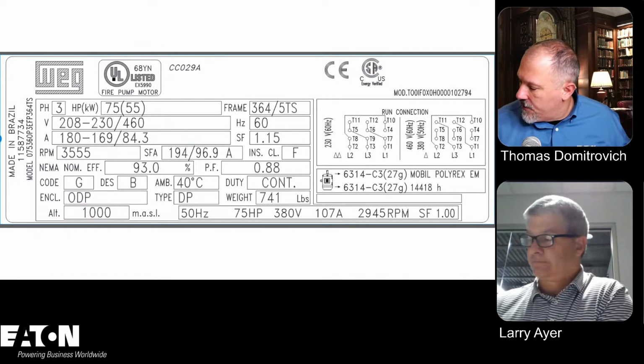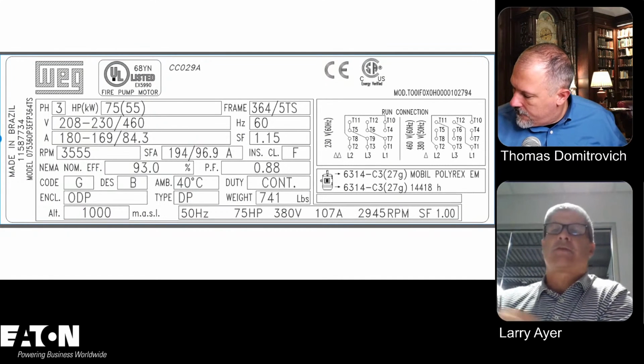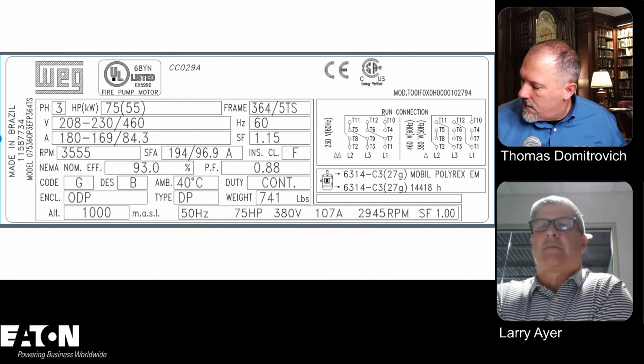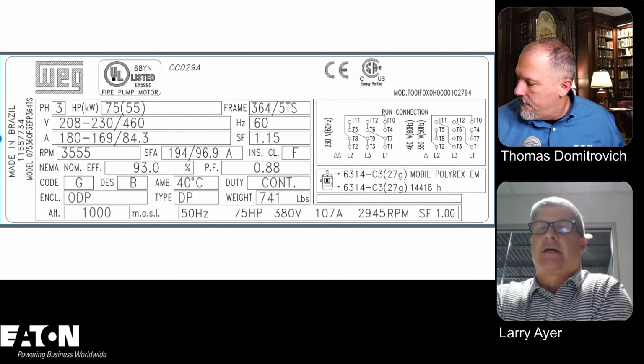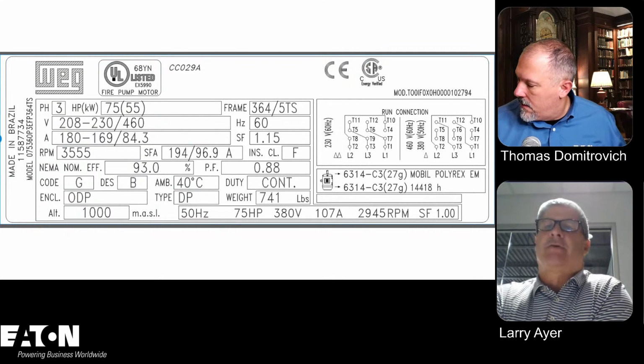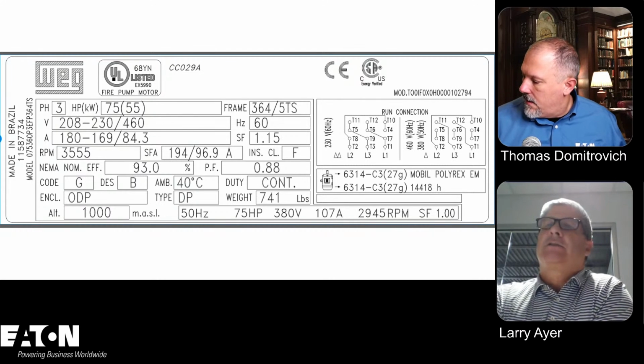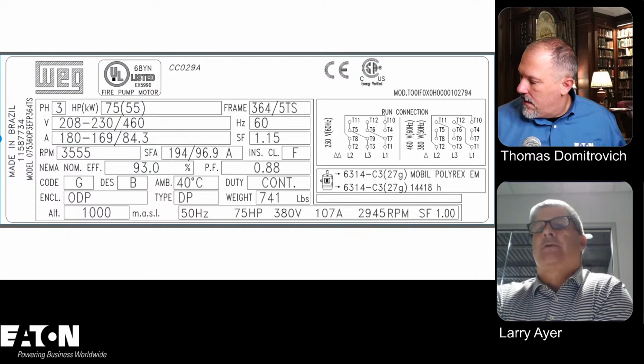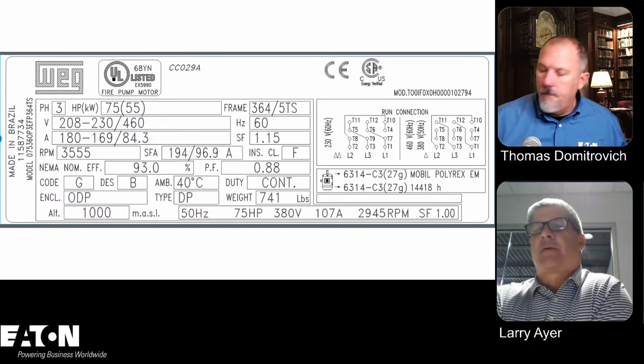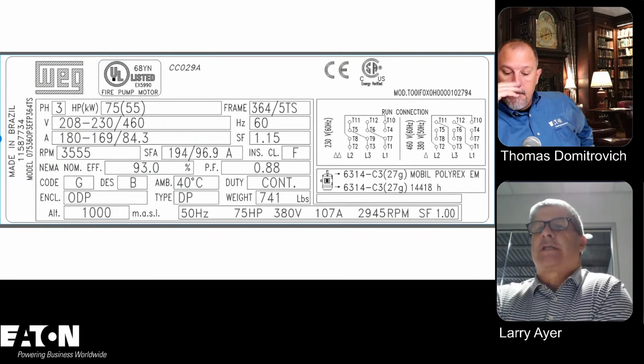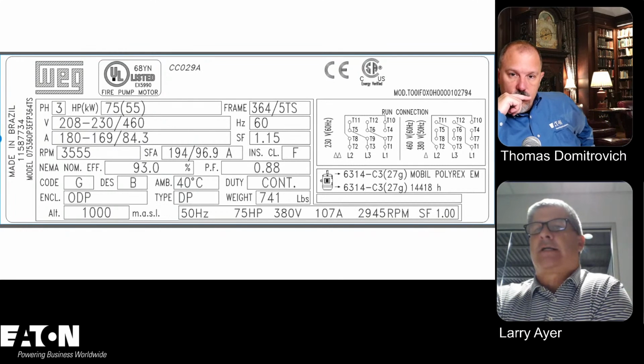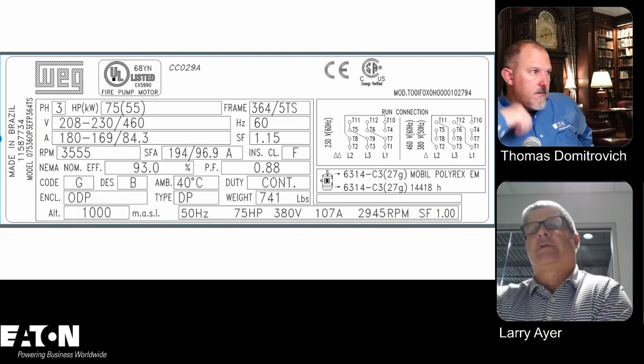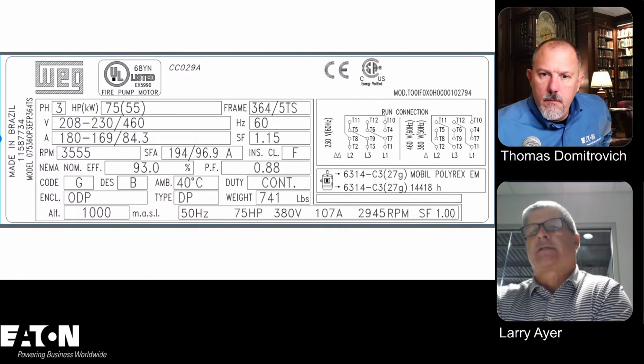All right. So now you're going to run through an example, right? Well, this is just to look at this nameplate. This is a nameplate of a fire pump we just did recently. Let's just concentrate on a 230 volt motor. This has an amperage rating of 169. So if you were to wire that fire pump, you would take that 169 and mark it up 125%. You would pick your wire. If you want to look at fault current, just to get you in the ballpark, you would take 6 times the 169 to consider your fault current.